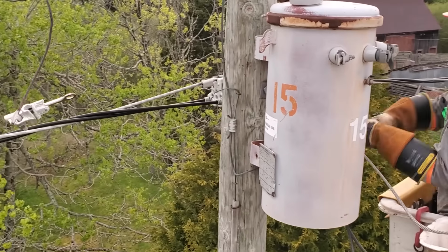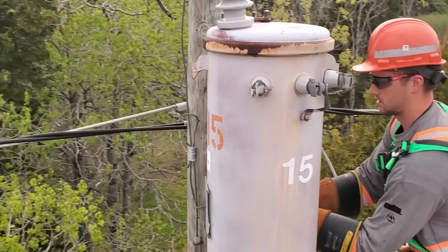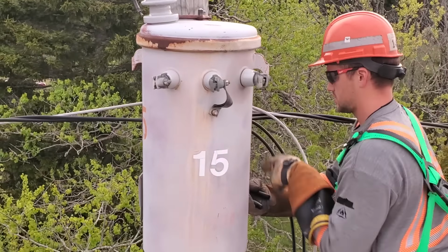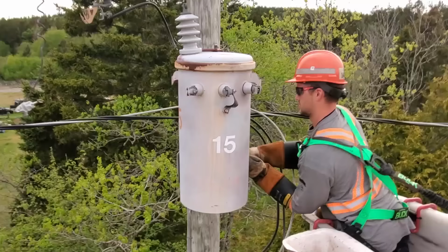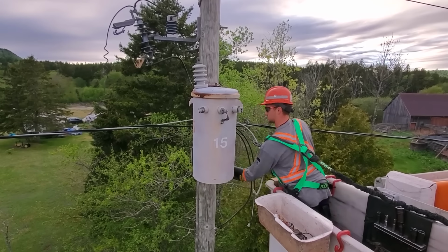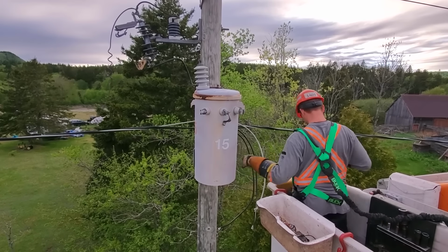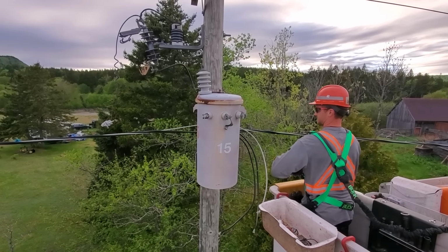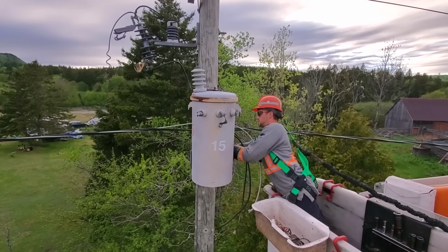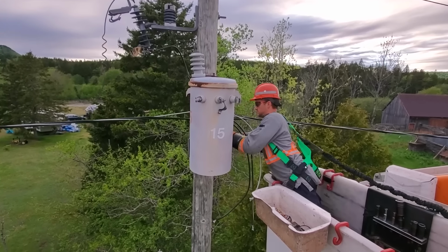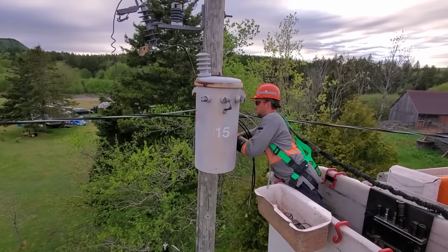So he's already got the transformer pretty well all taken apart here. There's no H2 on this transformer. It's actually using the secondary bushing, the X2, as the H2 for the path for the primary winding. The new transformer will have an H2 connection. Did have a case ground, however, which he has already removed.